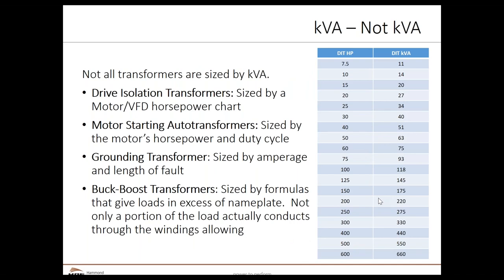There are cases where kVA alone is not how we size the device. Drive isolation transformers are sized by motor horsepower — as we say, don't be smart, use the chart. The kVA of a drive isolation transformer is derated to handle the proper load. For example, 100 horsepower is roughly 75 kVA, yet we suggest a 118 kVA drive isolation transformer, because of additional heating from harmonics. Motor starting auto transformers are sized by the motor's horsepower and duty cycle — how many starts per hour.